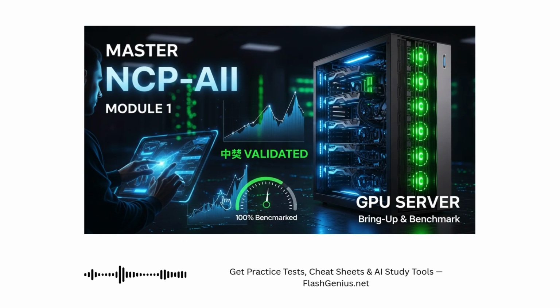You have to keep the GPU temperatures consistently below the throttling threshold, which is usually around 83-85 degrees Celsius. So under a full burn-in, you want to see the GPUs running comfortably in the 70s. You want at least a 10-degree safety margin. And how do we track this? Continuous monitoring with NVIDIA-SMI or NVSM during the stress test. If you see a GPU hitting 90 degrees, that points to a local cooling failure. A bad fan, blocked airflow.